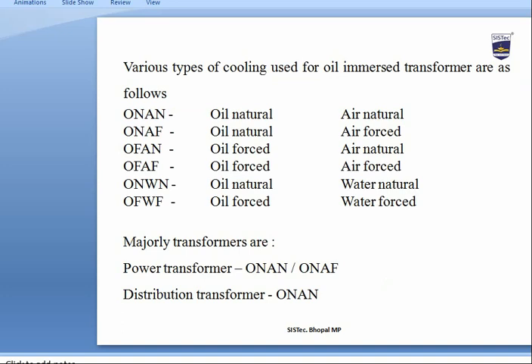For oil-immersed transformers, cooling types include: ONAN (Oil Natural Air Natural), ONAF (Oil Natural Air Forced), OFAN (Oil Forced Air Natural), OFAF (Oil Forced Air Forced), and ONWN (Oil Natural Water Natural). Power transformers are typically provided with ONAN and ONAF cooling, while distribution transformers use ONAN.